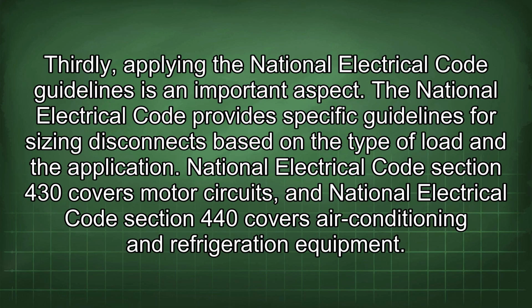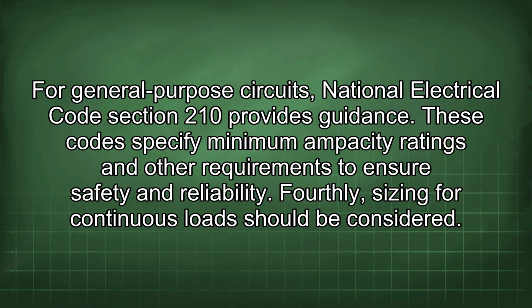Thirdly, applying the National Electrical Code guidelines is an important aspect. The National Electrical Code provides specific guidelines for sizing disconnects based on the type of load and the application. National Electrical Code Section 430 covers motor circuits, and Section 440 covers air conditioning and refrigeration equipment. For general-purpose circuits, Section 210 provides guidance. These codes specify minimum ampacity ratings and other requirements to ensure safety and reliability.